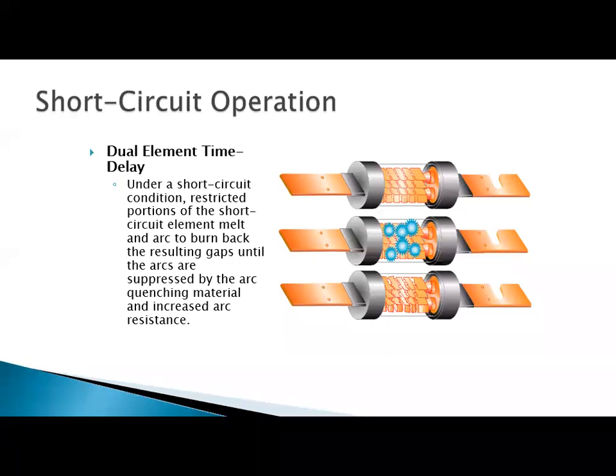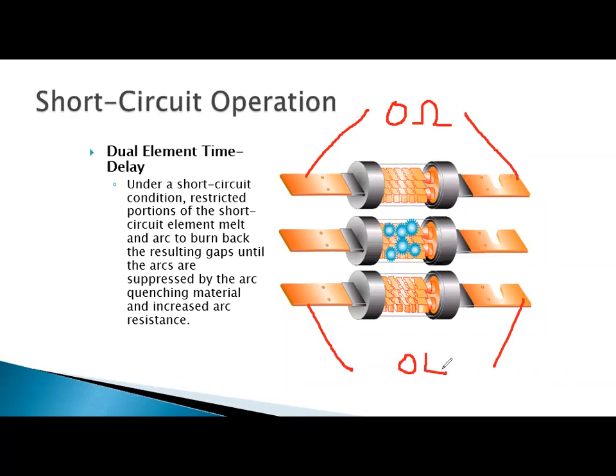So right here, I do want to say this, that if I did want to check one of these fuses when they were out of the circuit, I could go ahead and put my ohm meter on one side or the other. And if I saw something close to 0 ohms, of course, I would know that fuse was good. If I did that same test and I saw OL on my meter, which is open line, then I would know that fuse had opened up that circuit. And towards the end of the presentation, I am going to give you an idea how OSHA does allow us to test these fuses while they are energized. So I'll definitely go through that also.